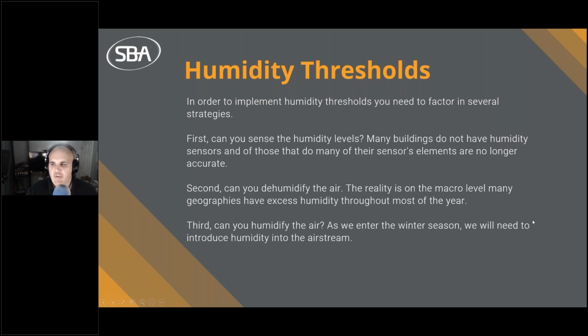Third, and this is something I don't hear enough people talking about that we need to be considering, especially since we are rapidly approaching the winter time, is can you humidify the air? So as we enter the winter season, this is time to go check those Nortec humidifiers and actually make sure they work. Because we all know how many buildings have a humidifier installed in the airstream that they've literally disabled and have never run because it's a pain to maintain and it's a pain to control because it can easily overshoot the humidity values. So, can you humidify the air? You need to be cognizant of this, especially if we are going to be implementing more outdoor air centric control.